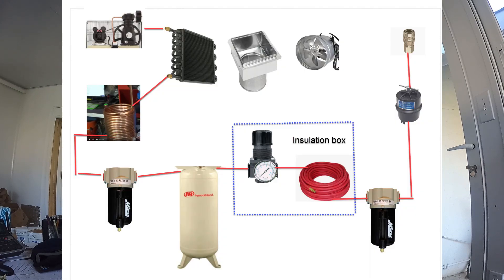Extend the length of the condensation coil — i.e. dwell — as required to get your desired results. Dwell is critical to performance. Place a water trap at the exit of this condensation coil. During the winter, you may have to remove the insulation from the coil to keep the water from freezing.